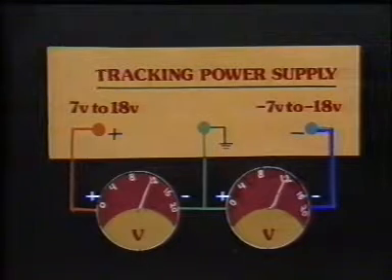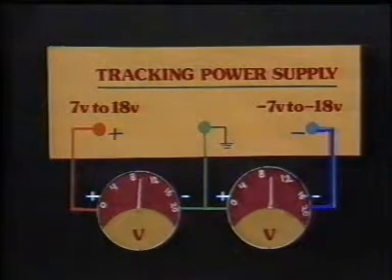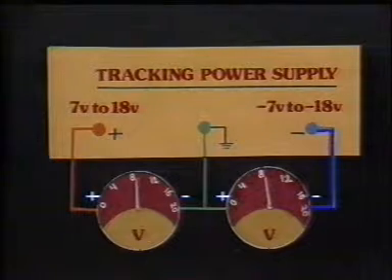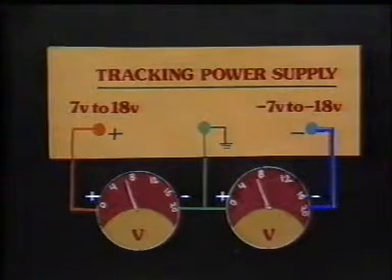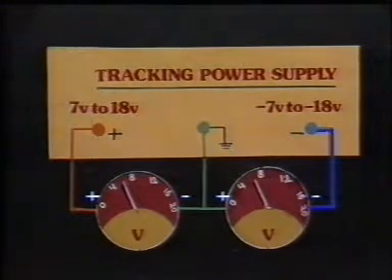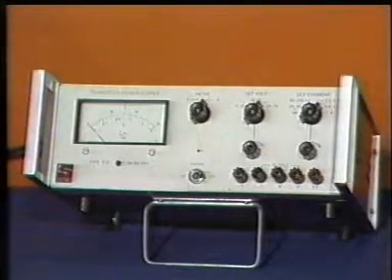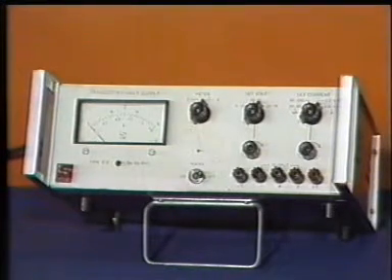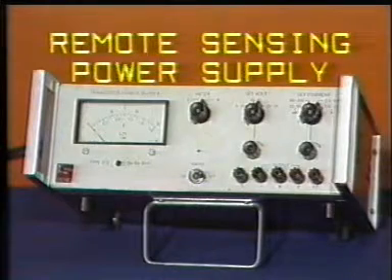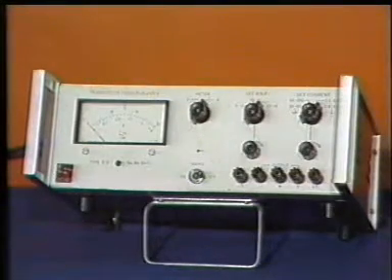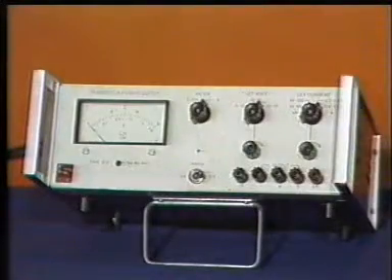Such power supplies are called tracking power supplies. When power at high current is required to be supplied at a fairly distant location, we use a remote sensing power supply, which through sense terminals maintains the desired voltage at the load regardless of the drop that occurs in the connections.